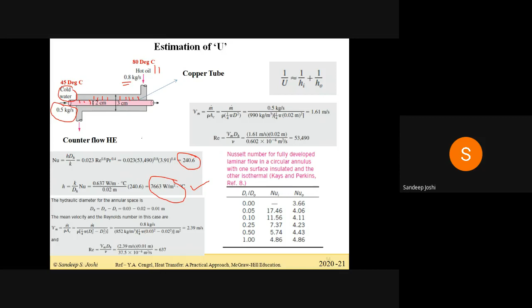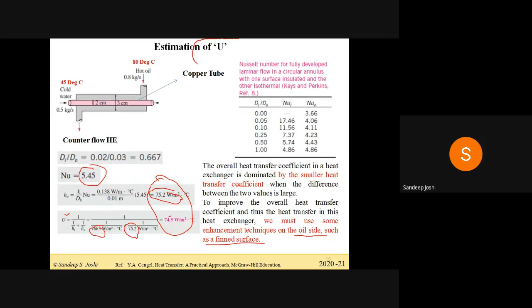Okay, because at the inner tube, the heat transfer coefficient is already more, so the scope of more improvement is less. If I put certain baffles from the inside, it will create turbulence, but it will again offer resistance to the flow, and it will increase the pumping power requirement. But on the other side, in the shell side, outside this inner tube, I can put certain fins. These fins will act as heat transfer enhancers, so those will increase the rate of heat transfer here. So as the heat transfer coefficient at the outer side is less, it is recommended that you use enhancement techniques like fins in this heat exchanger on the oil side. Okay, so this is the example of the estimation of U, the overall heat transfer coefficient.